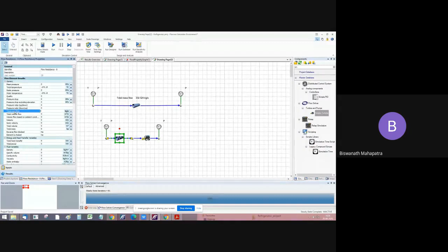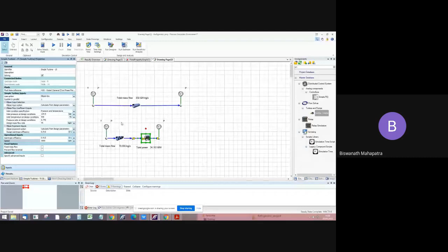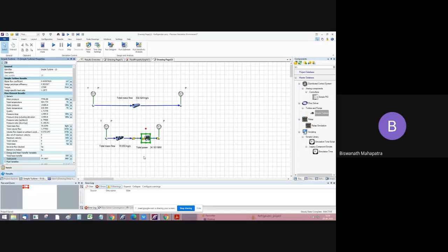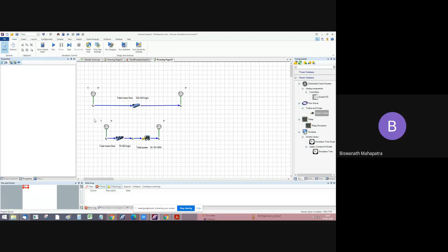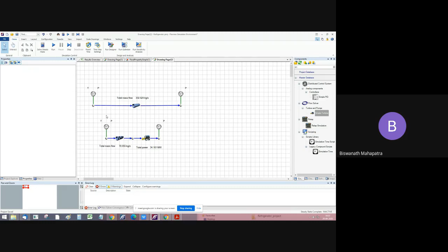Now I can monitor my parameters, like the mass flow through the valve and the total power output of my turbine. Now I'm going to solve steady state. You can see that according to our specified inputs, 70 kg per second of steam is flowing through the valve to the inlet of the turbine. Then the power of the turbine is 34 megawatt, meaning the power the turbine produces to rotate the shaft is 34 megawatt. This is how we build a model according to our specific inputs, or if we are performing some experiments. From the experimental data we have, we can model Flownex networks accordingly.